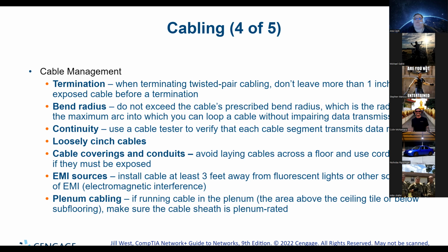Continuity, use a cable tester to verify that each cable segment transmits data reliably. Loosely cinch cables. Now, I've seen a lot of times where people have come into data closets and just shoved cables under stuff and bent and kinked and crunched, and then the cables have to be repaired later. So it may not be the initial person's fault, but be aware that crunching and cinching cables is not good for them. Cable coverings and conduits, avoid laying cables across the floor, and use cord covers if they must be exposed.